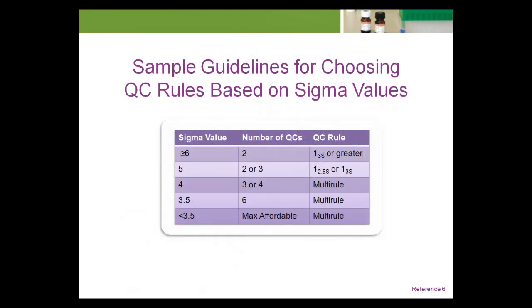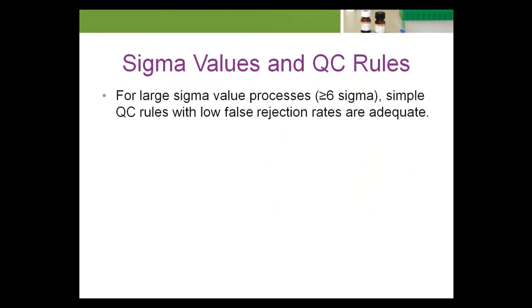Simple guidelines for choosing appropriate QC rules based on sigma values have been proposed, and an example of one such guideline is shown here. For lower sigma values, more QC samples and more powerful QC rules are recommended. Note: a 1-3-S QC rule rejects if any of the QC results differ from their target concentration by more than 3 SDs. Multi-rules are combinations of individual QC rules that tend to be more powerful than simple rules such as the 1-3-S QC rule. For large sigma value processes (greater than or equal to 6 sigma), simple QC rules with low false rejection rates are adequate.